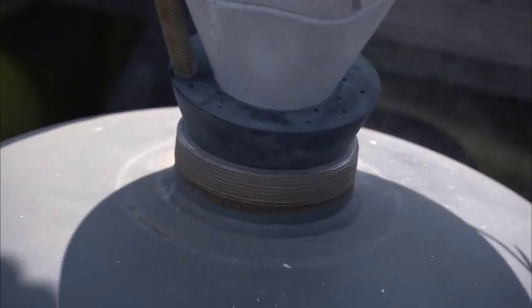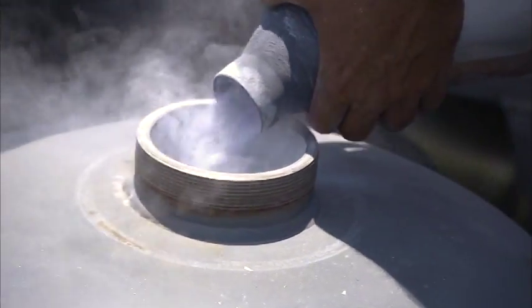Dry chemicals are abrasive and corrosive and leave a residue. At least one ARFF vehicle required by the index must carry sodium-based dry chemical, potassium-based dry chemical, or an approved halogenated agent such as Halon 1211 or Halotron I.